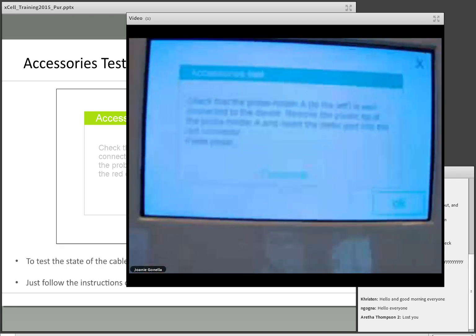Essentially, you go through this and you're going to test every cord. The main thing you have to understand with the accessories test is that you need both ends of the cord to be connected to the machine somehow. So if it's the red cord, if it's the black cord, both ends have to be put into the machine. If you don't have that, then it's not going to show it as functional.